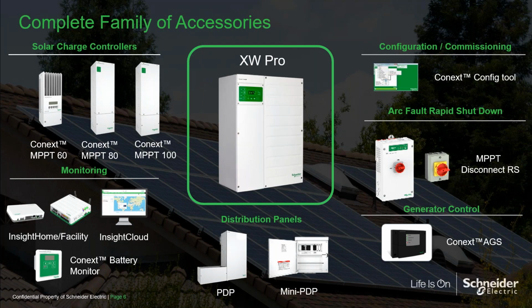charge controllers. Finally, the automatic generator start offers automatic starting and stopping of a generator with voltage or state of charge triggers available. It should be noted that XW Pro and AGS work very well with generators. In fact, the system is smart enough to shut down the generator when the grid returns. This is because XW Pro has a separate input for grid and a secondary input for a generator. You can even change the AC association in case you want to integrate 2 generators.